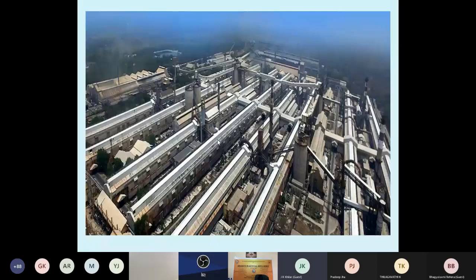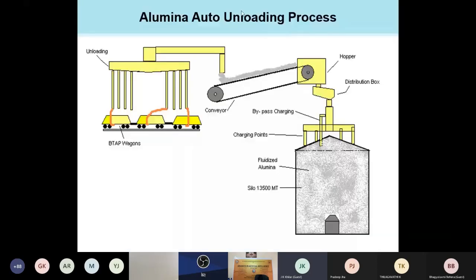So when alumina powder is coming from Damanjodi by rail, the operator has to select which silo is empty and feed the alumina powder. Suppose silo number 1 is empty, and we have to fill it with alumina powder. So first the valve will open. Then the conveyor belt will run. After the conveyor belt is running, the indication comes to the PLCs. Then the compressor will start.